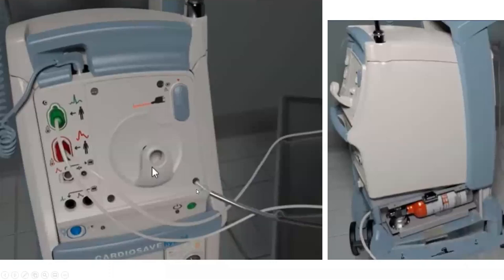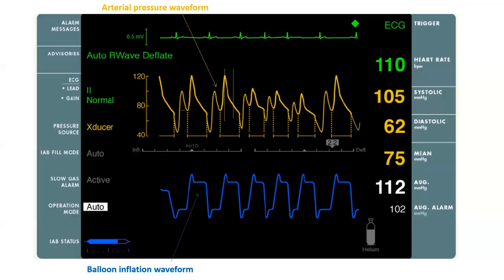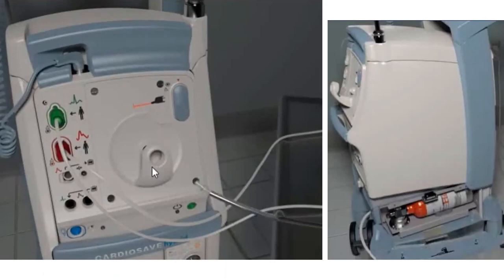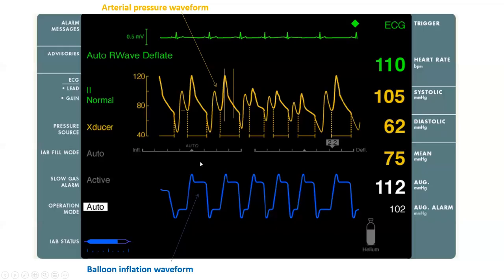Also in the console, this is the port where you connect that helium line. And on the side of the console, you can see where the helium canister is. Those are important to know in case there is troubleshooting of the balloon inflation. You always verify the connections are proper. You verify you have a good canister of helium. And I will explain that further. I will move on to describe the waveforms.